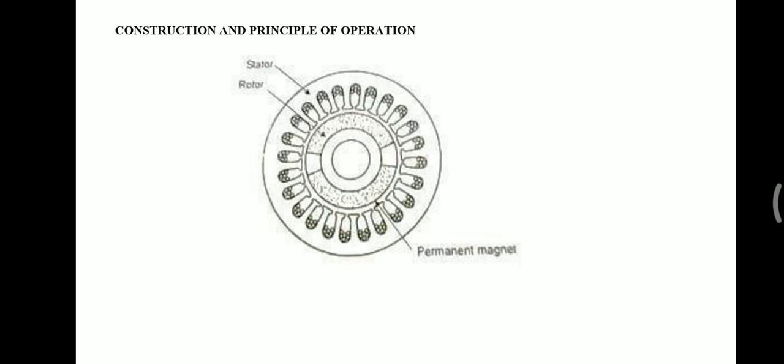Permanent Magnet Synchronous Motor is also called Brushless Permanent Magnet Synchronous Motor. It features sinusoidal or quasi-sinusoidal distribution of magnetic flux, sinusoidal current waveforms, and sinusoidal distribution of stator conductors with short-pitched and distributed or concentric stator windings. The quasi-sinusoidal distribution of magnetic flux around the air gap is achieved by tapering the magnet thickness at the pole edges and by using a shorter magnet pole, typically 120 degrees.